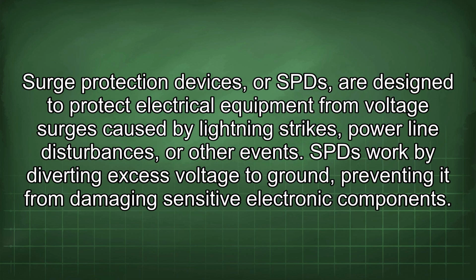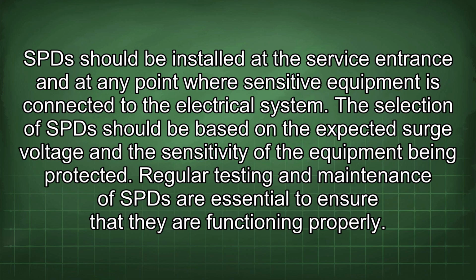Surge protection devices, or SPDs, are designed to protect electrical equipment from voltage surges caused by lightning strikes, power line disturbances, or other events. SPDs work by diverting excess voltage to ground, preventing it from damaging sensitive electronic components. SPDs should be installed at the service entrance and at any point where sensitive equipment is connected to the electrical system. The selection of SPDs should be based on the expected surge voltage and the sensitivity of the equipment being protected. Regular testing and maintenance of SPDs are essential to ensure that they are functioning properly.